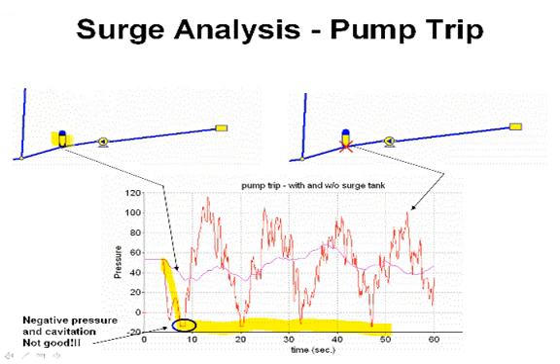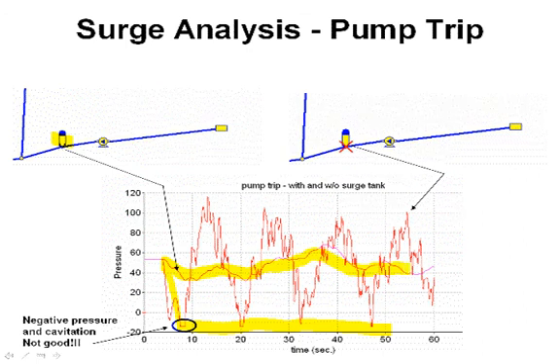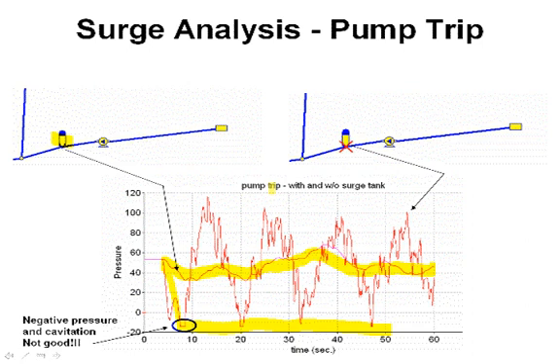If you put a surge tank in, when the pump trips, the surge tank can provide water to the system and you get a very smooth transition. You can evaluate this with your computer model. This is why you absolutely have to have a computer model to understand and operate your water utility in an efficient and effective manner.